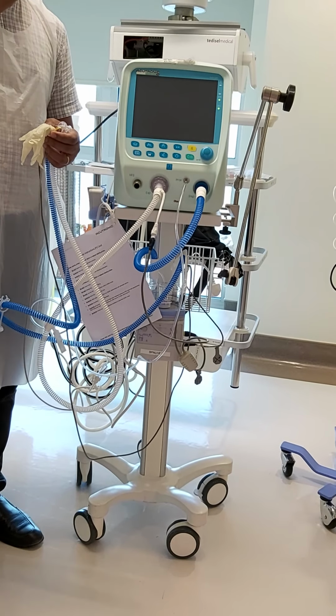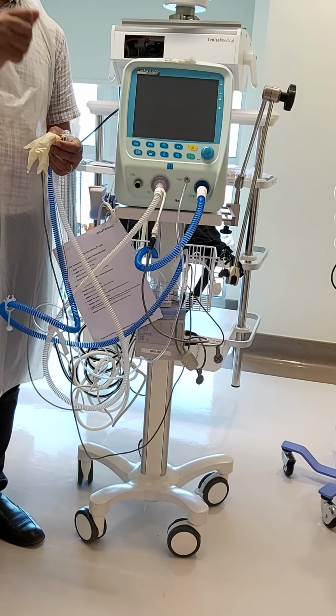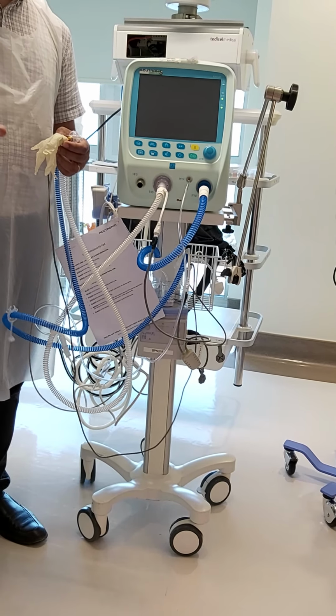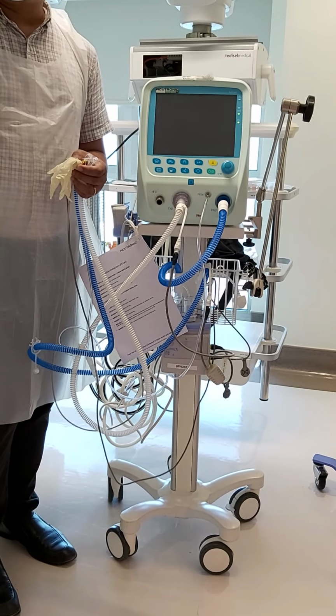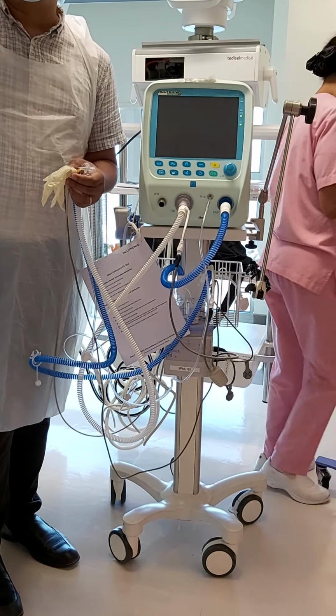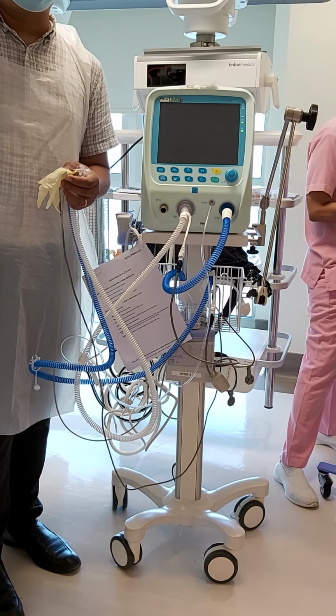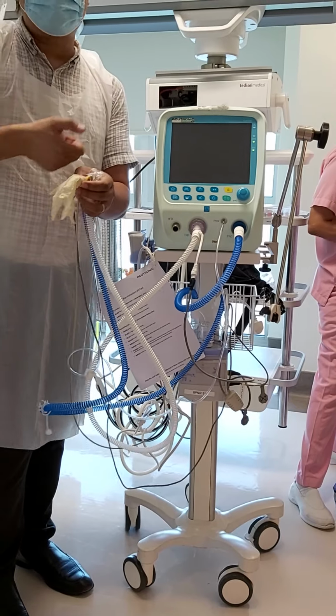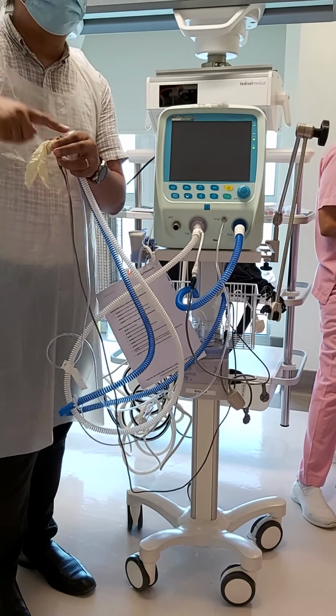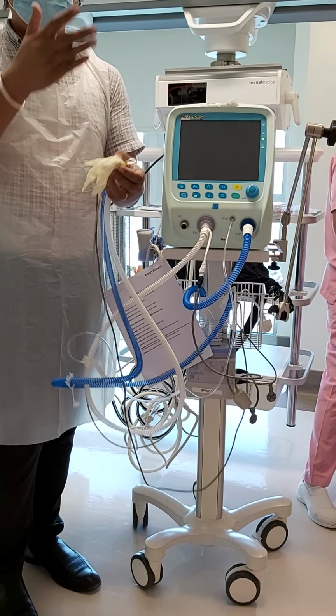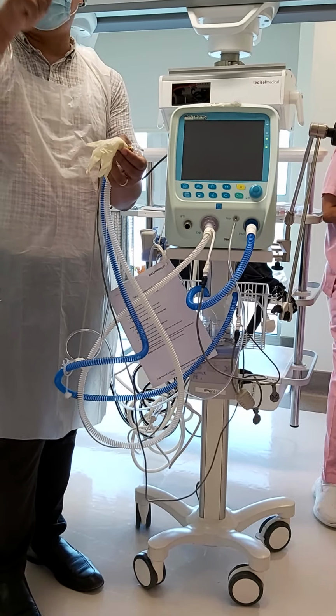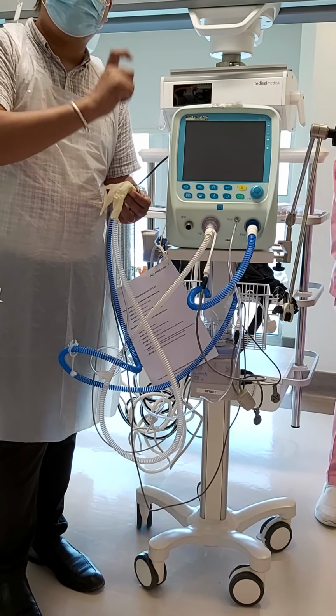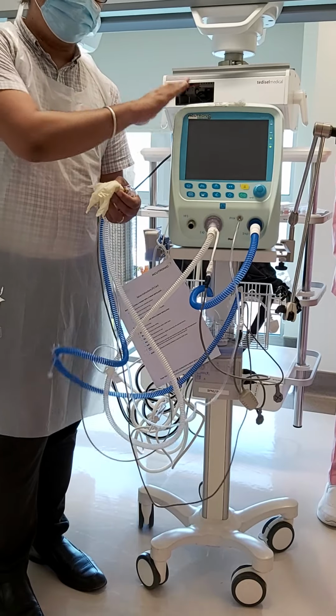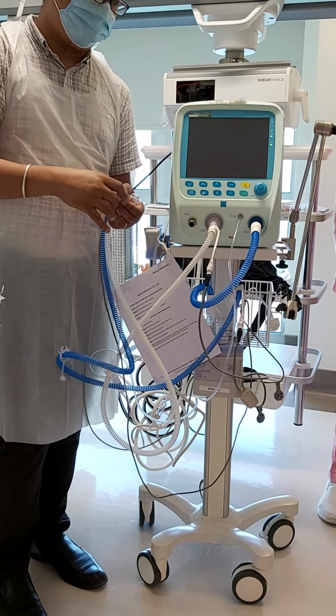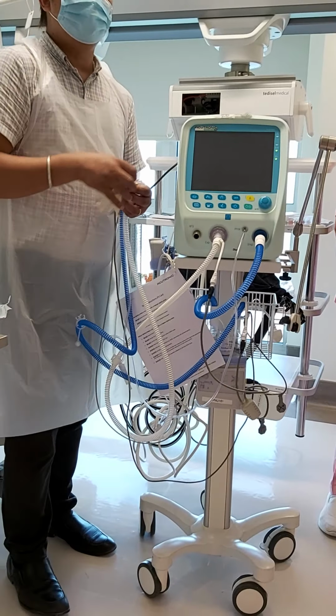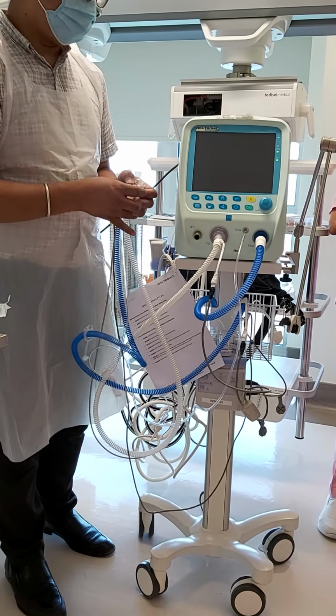Now, there are two types of HFO available in the market. One is what we call flow trigger, that is in your Draeger. Flow trigger, it's like when you're watering the plant and you want to reach a certain part of the garden, what you do is you pinch, you press the end of the hose so the water will shoot up. It's the same as the flow trigger. Okay? The flow trigger does like this so that you will have oscillation. For this one, you have something that really push and pull. So that is the difference. This one really pushes the pressure inside the patient. Okay, so that's why most of the doctors, they like Acutronic or Sensormedics. These are the two things that they have.